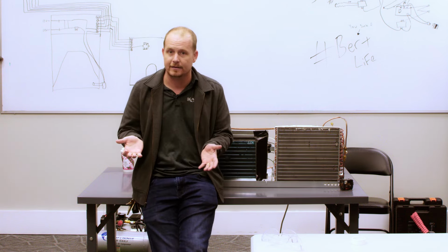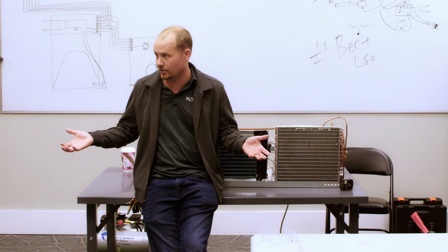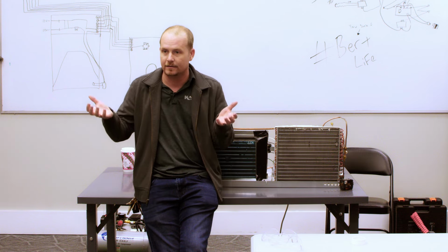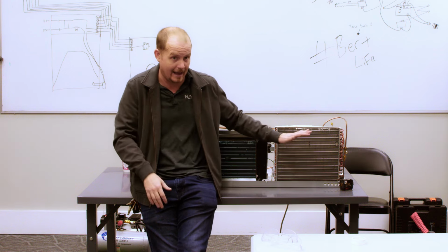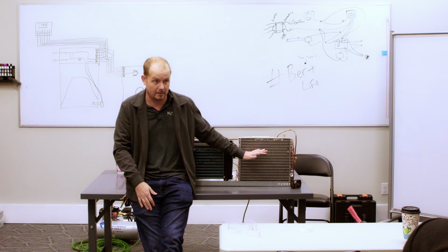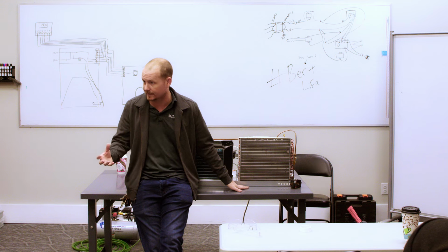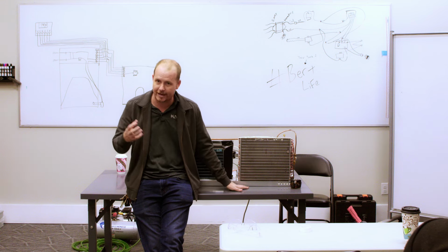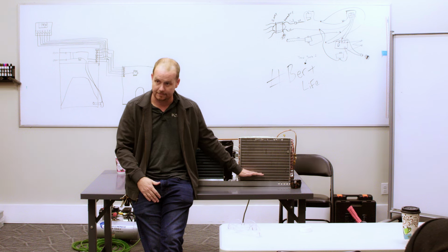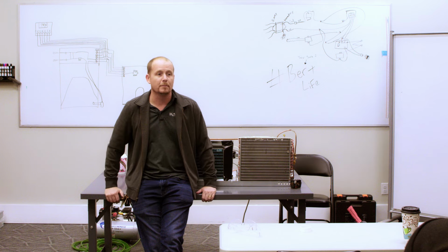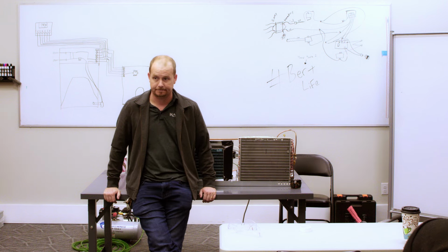because you still have vapor and liquid mixed. Another name for that is zero subcooling. Another name for that is still at saturation, meaning it has not fully condensed. It is not 100% condensed. It doesn't mean it hasn't been condensing, because it has, because it's mostly liquid still. It's very rare that you're going to find a sight glass that's mostly vapor. It's still mostly liquid, but it hasn't fully changed to have a complete liquid seal in the bottom of this condenser.